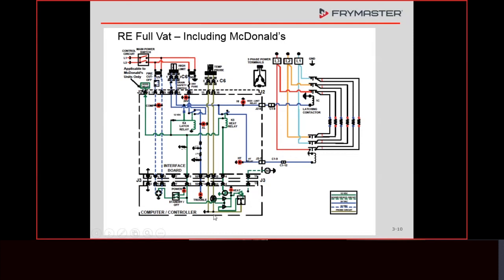Whenever this resistance is lower, it's going to call for heat, meaning, when we turn the fryer on, we have 12 volts DC because it goes through a rectifier, 12 volts DC that comes up here to the latch relay. That relay is going to pull in. On our electric fryers, as soon as you turn the fryer on, the contactor pulls in because this relay pulls in. It's already grounded. The heat relay is looking for that ground that it's only going to get whenever this resistance is lower than this resistance. Then it knows in order to get this resistance higher, we need heat. It gives the ground to this relay.